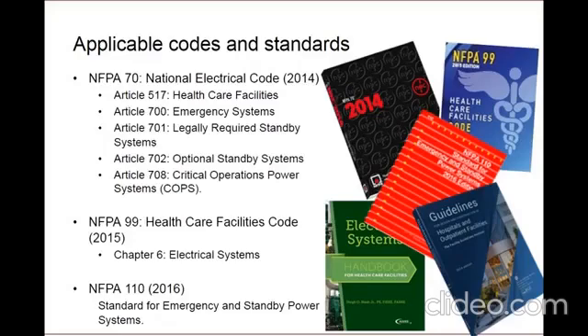So hospital electrical systems are definitely complex and subject to a plethora of codes and standards. So we'll start with just the NFPA codes. First, you have NFPA 70, and within this code, there are several applicable articles dealing with healthcare facility design. Those include Article 517, which is really the meat of the requirements for healthcare facilities, but the engineer must also be familiar with the Chapter 700 articles, including 700, 701, 702, and sometimes even 708. Then you have NFPA 99, which is the Healthcare Facilities Code, and it focuses on all systems in healthcare design, including medical gas installations, HVAC requirements, and so on. Chapter 6 of this code is specific to electrical systems, which is what we will focus on today.